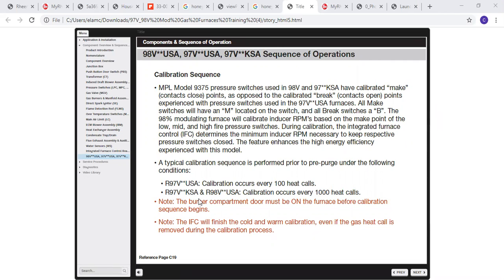You'll see here at the bottom, the calibration occurs on the original R97V USA every 100 heat calls. On the newer R97 KSA and the R98V USA, the calibration occurs every 1,000 heat calls. So what the calibration sequence is, it learns how to match the RPMs of the inducer motor to make or break the pressure switches.